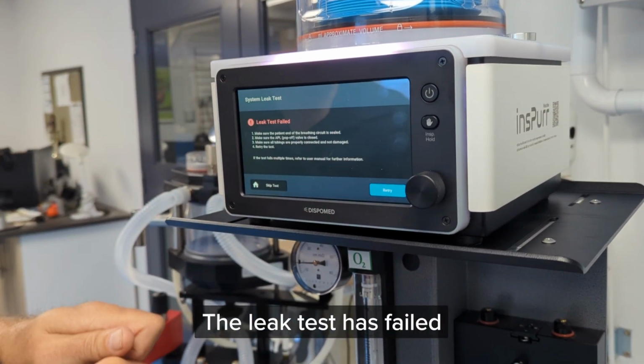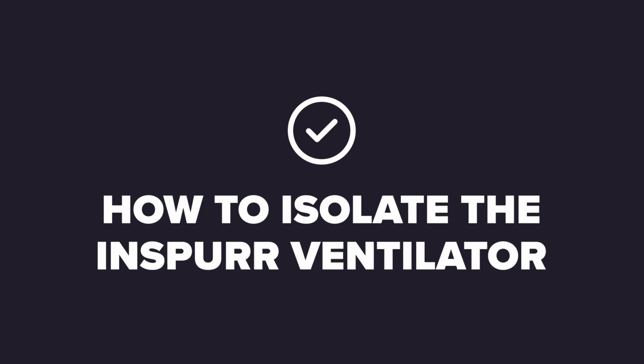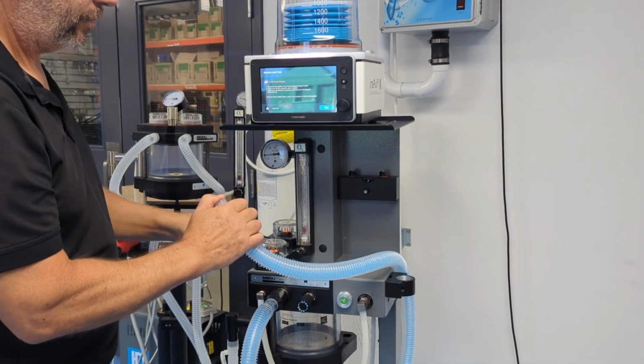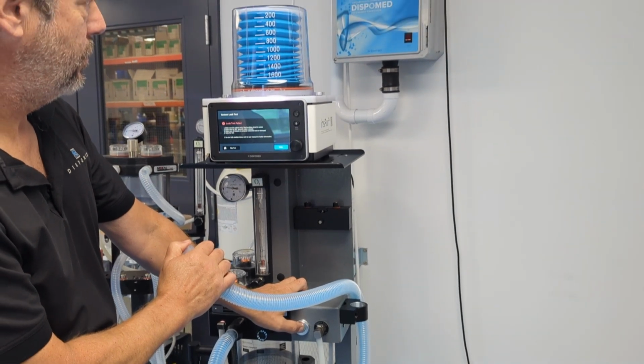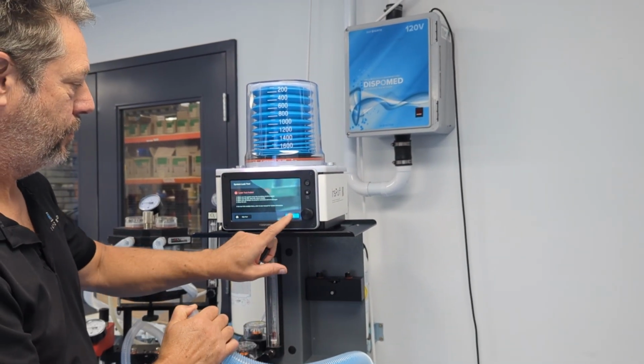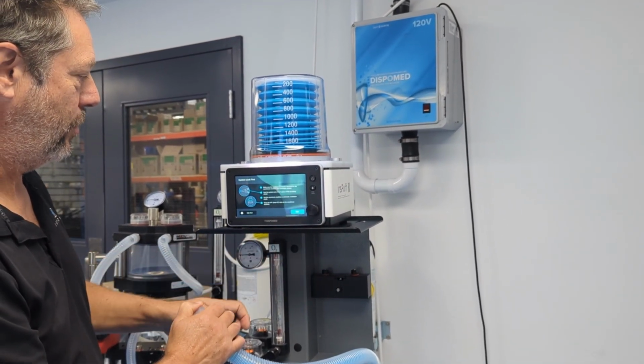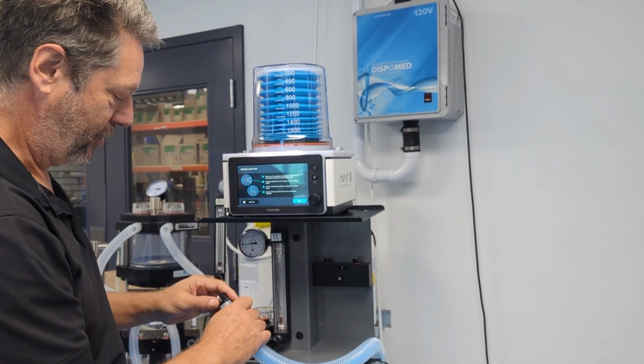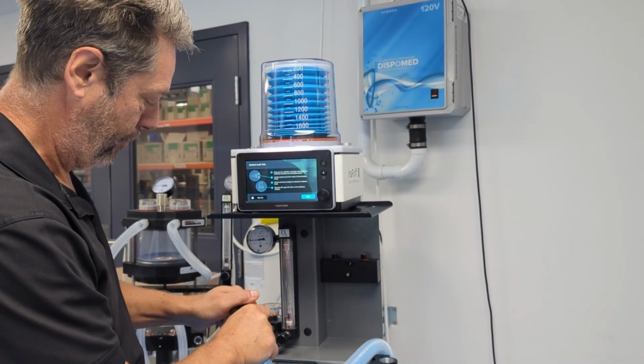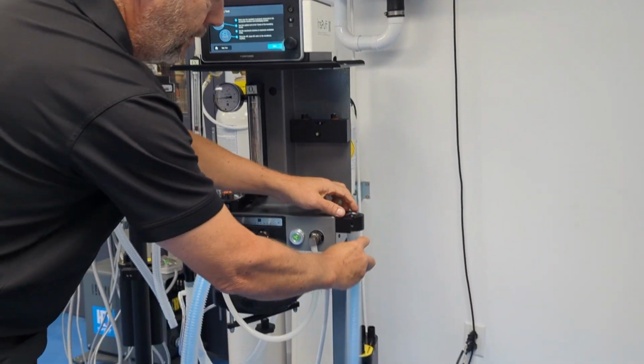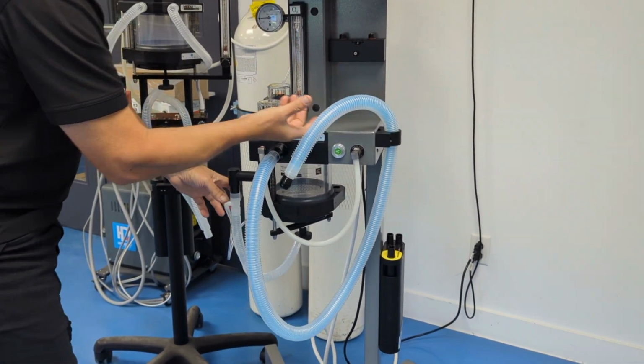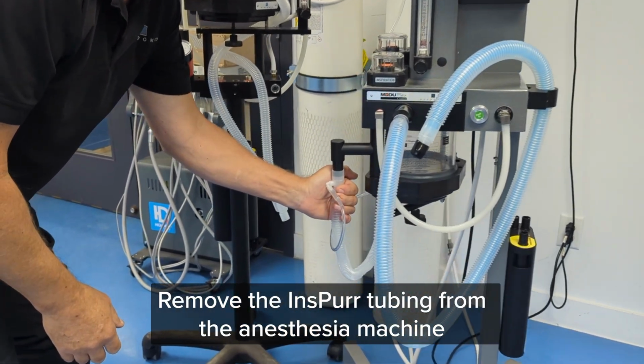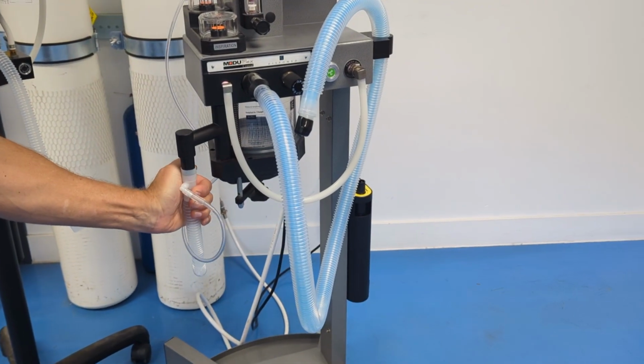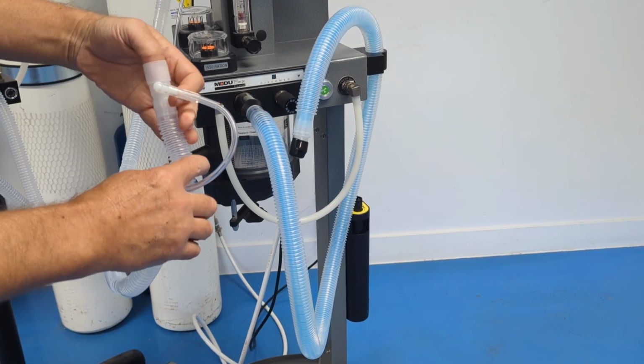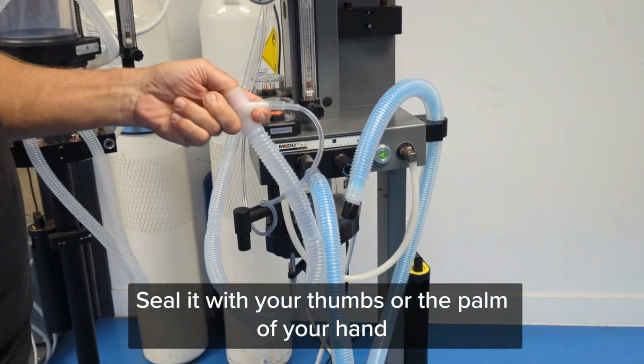The leak test has failed. How to isolate the insPurr ventilator. Follow the leak test steps again. Remove the insPurr tubing from the anesthesia machine. Seal it with your thumbs, or the palm of your hand.